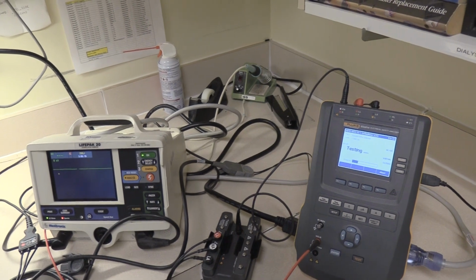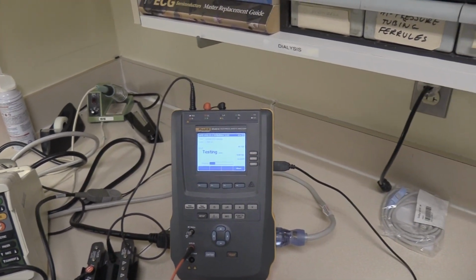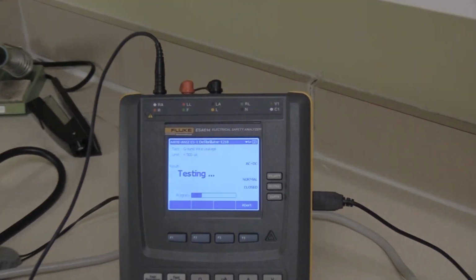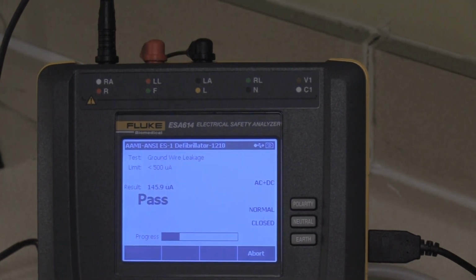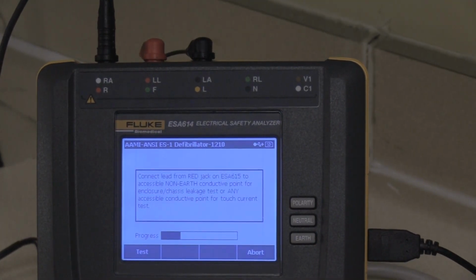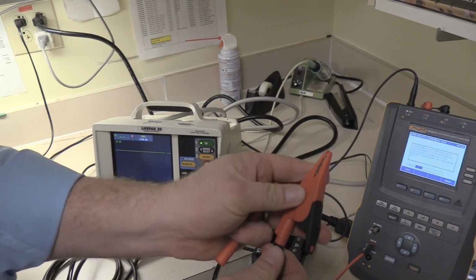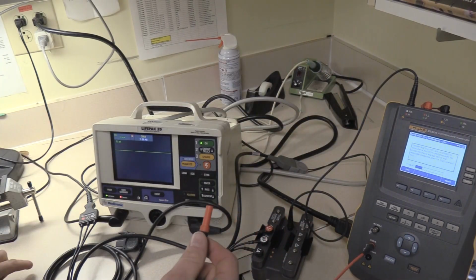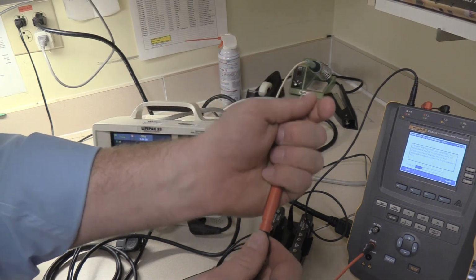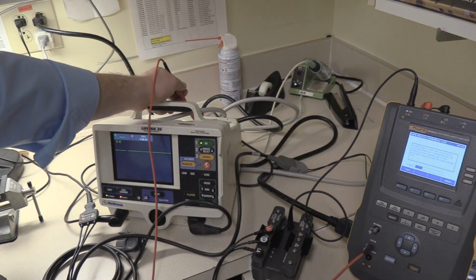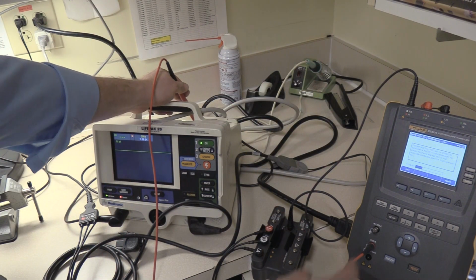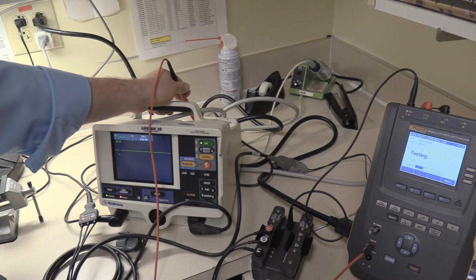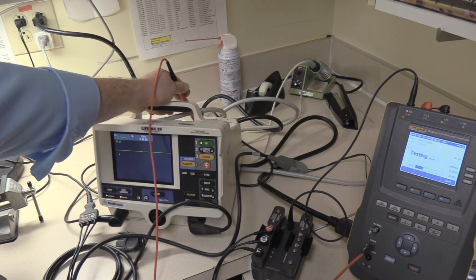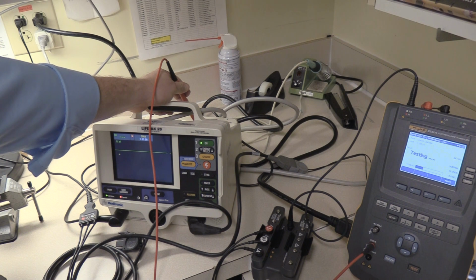Now these are conducting all the tests that we have pre-programmed in. And we can see them going through. And now it wants us to move the red cable from the ground pin to a non-earth conductive point. This is simple. And put on this hand probe. And what I'm going to do is use the defib discharge points on the top of the LifePak and hold this red cable through the rest of the test. Push F1 for start. And we're going to resume the test.